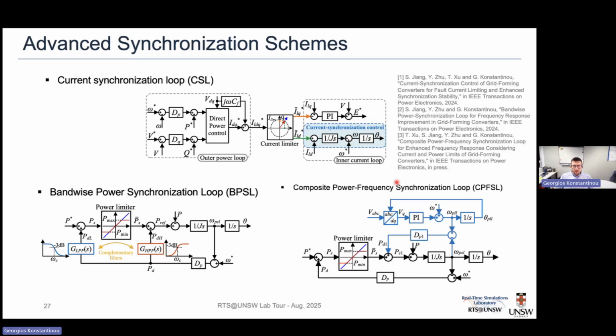So this goes back to some of the research that we are doing ourselves with our research group here, that allows us to look at different options on how we can control and how we can regulate this self-synchronization aspect of grid forming converters. Some ideas that we have put forward here, I'm trying to summarize them quickly. One of them looks at moving the synchronization loop from the outer part here, directly acting on the voltage and the angle, inside the current control structure and after the current limiter. So in what we call the current synchronization loop, it avoids some of the synchronization challenges that we have when we are limited to what we can do from the outer loop because of this current limiter that exists in the grid forming converter.